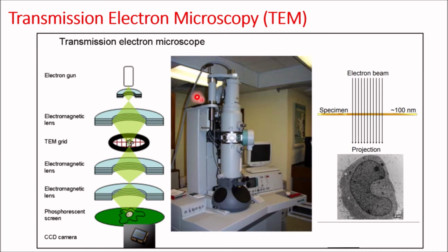In the area of the electron source, a vacuum of 10 to the power minus 7 to 10 to the power minus 10 millibar is necessary to prevent oxidation or burning of the heated filament. The column and the area of the specimen are evacuated to a vacuum of 10 to the power minus 5 to 10 to the power minus 7 millibar, which corresponds to a mean free path greater than 50 meter. Any collision with a residual gas molecule in the system reduces the resolution and the performance by the scattering of electrons. So to avoid such scattering, the system is kept at very high vacuum.